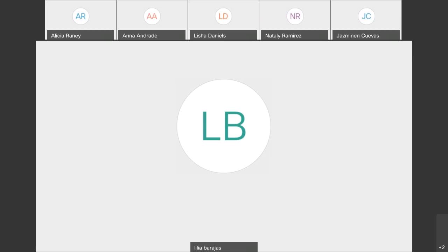All right, very good. Urine analyzers. Urine analyzers are used to perform an automated chemical examination of urine with reagent strips. They offer the advantage of the ability to perform the chemical analysis quickly and to interpret results automatically. These analyzers are used most often in the medical office that performs moderate to large volume urine testing. The Clinitek Analyzer is an example of a urine analyzer that automatically reads Multistix and other urinalysis reagent strips. The results are printed out and abnormal results are flagged to call attention to them.